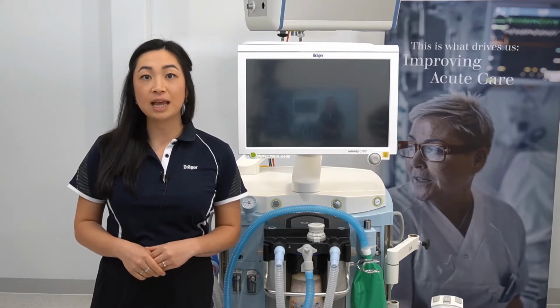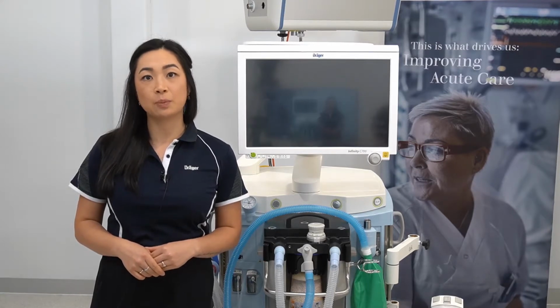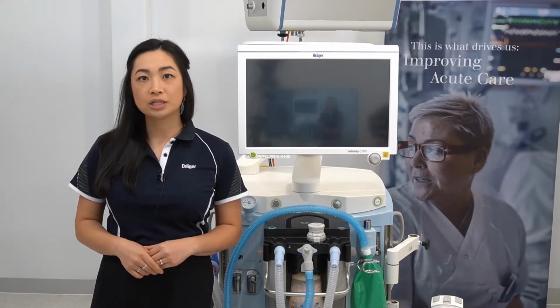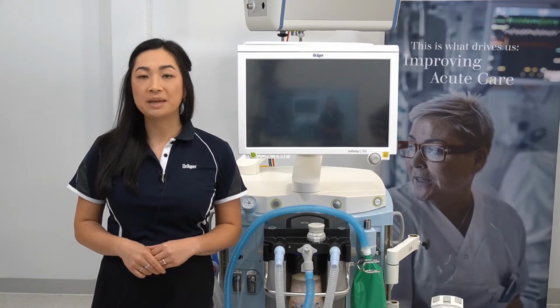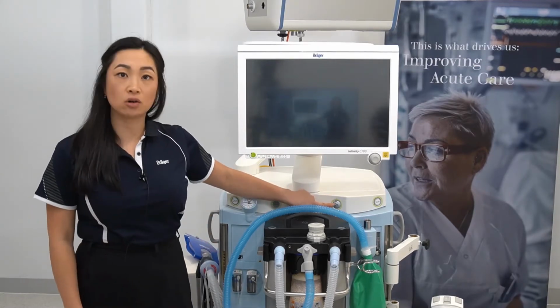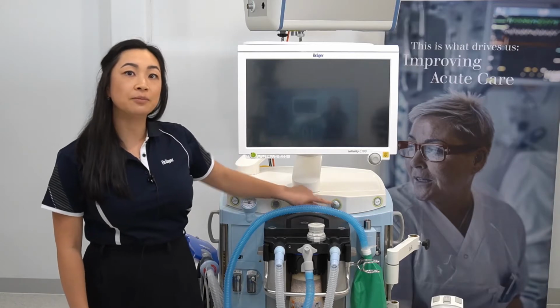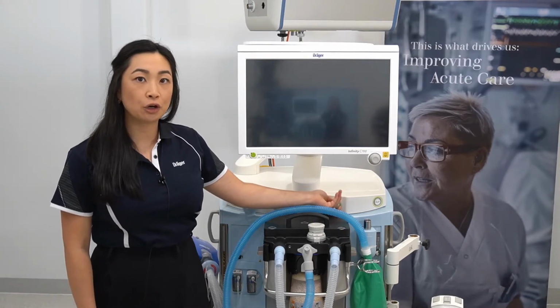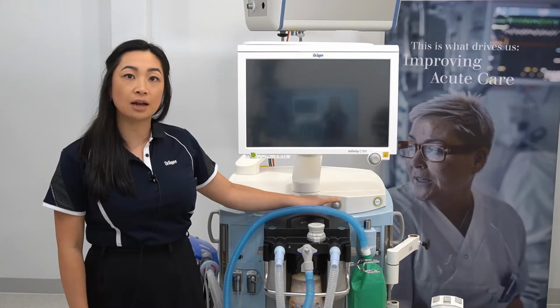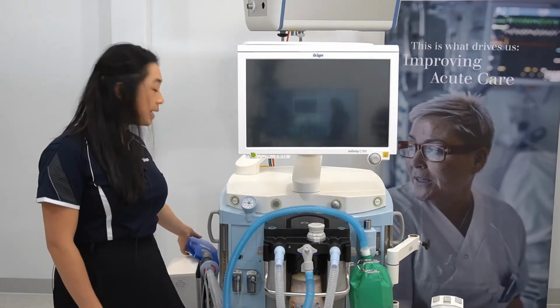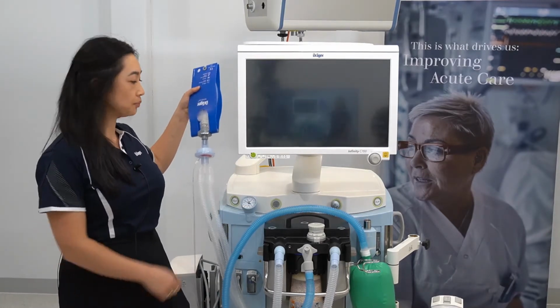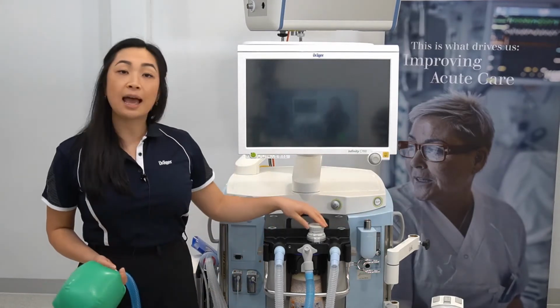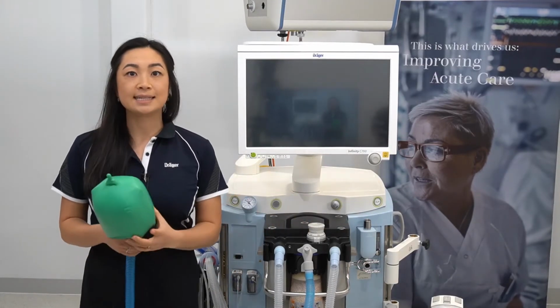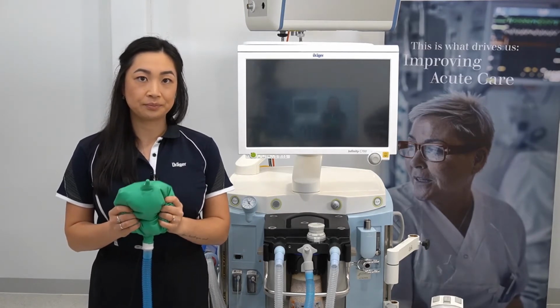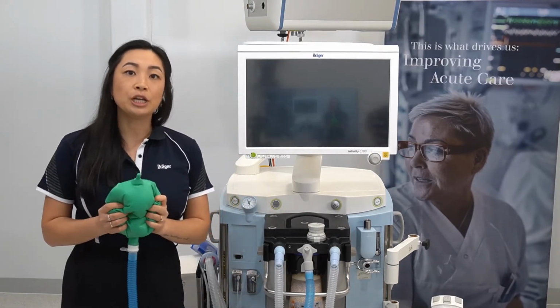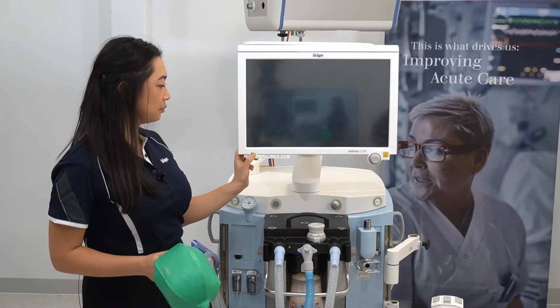Manual ventilation and emergency oxygen delivery is possible at all times. To perform an emergency startup, begin by opening the safety oxygen control knob by pushing it in, turning up to your desired flow with the flow indicated on the outside of the knob. Connect your patient up to the breathing circuit. Check your APL valve setting and start manual ventilation. At this point, you can then turn on your device.